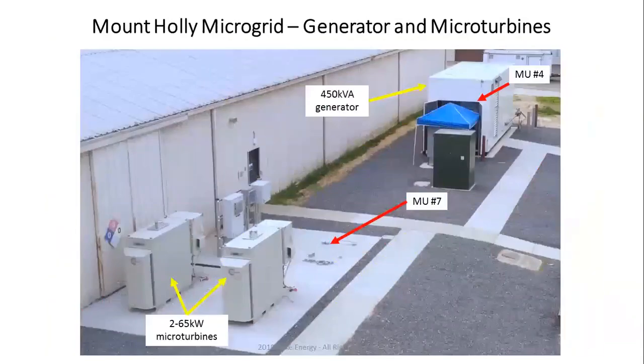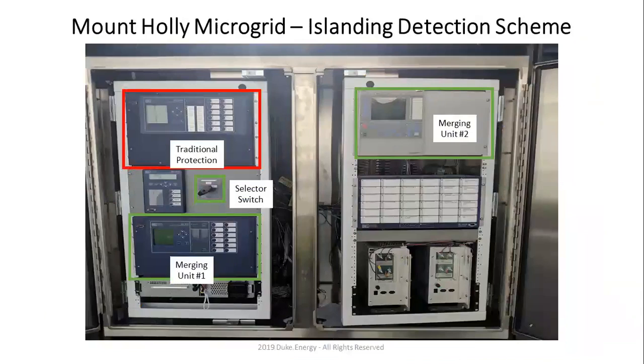There's nothing on the PV side. The generator has its own merging unit. And we're also waiting for merging unit number 7 for 2 microturbines, right? So all the work that we have done was with respect to all the merging units, excluding merging unit 7.